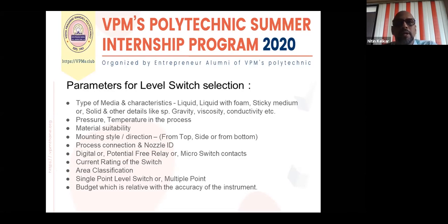So if somebody orders a 2-inch flange, and it does not have sufficient inner diameter, that can also become a problem. Take an example: the level switch has a diameter or size of, say, 2 inches, and the nozzle of the tank is just 1.5 inches or maybe 1 inch in diameter. The level switch cannot pass through that nozzle. So that also has to be given a thought before we select the product.